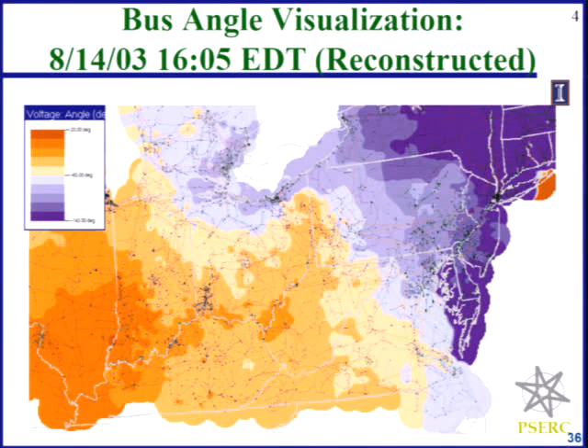This is that bus angle visualization I was telling you about. Over here, the dark orange represents an angle of 20 degrees on whatever reference scale you're using. As you go this way, the angles get lower, which is to be expected. Angles have to vary across the system because power flows from high angle to low angle. That's how, on a first approximation basis, it works.